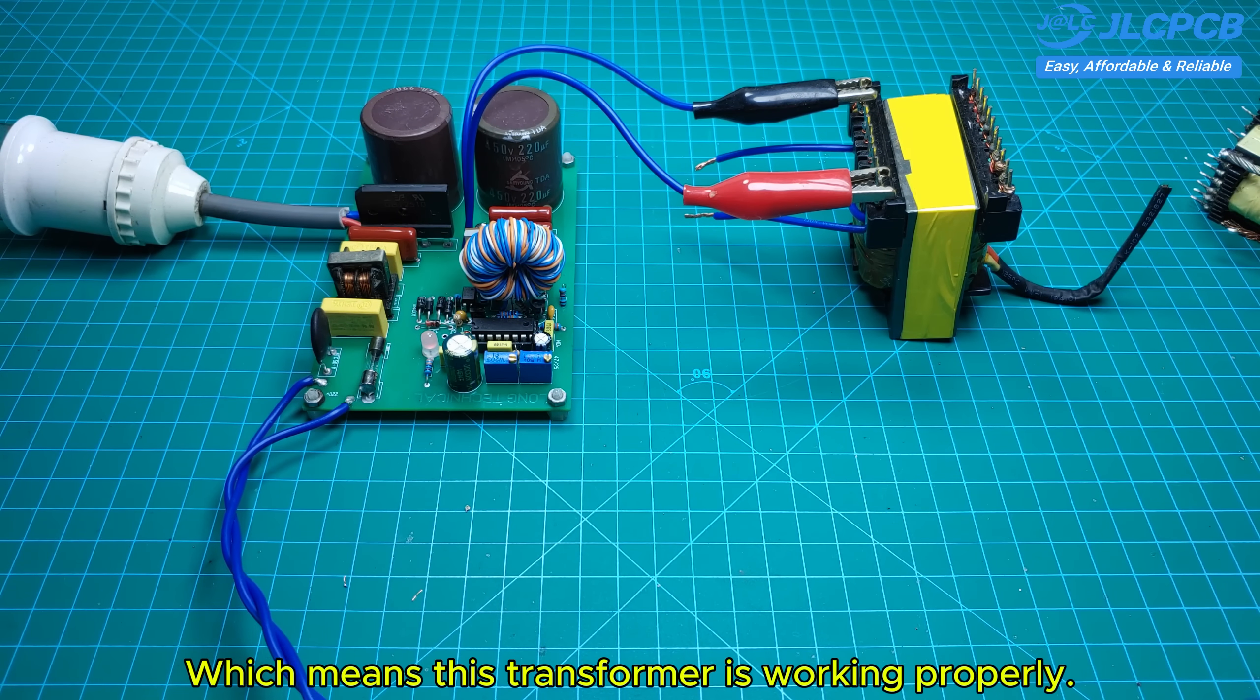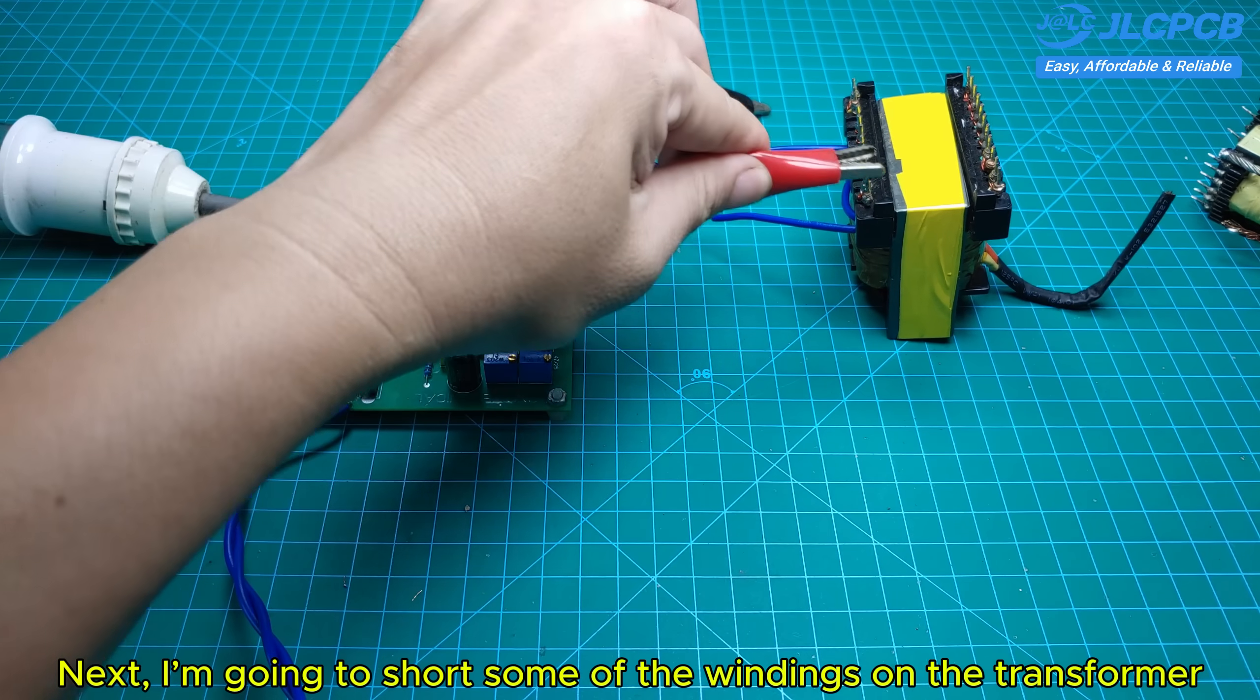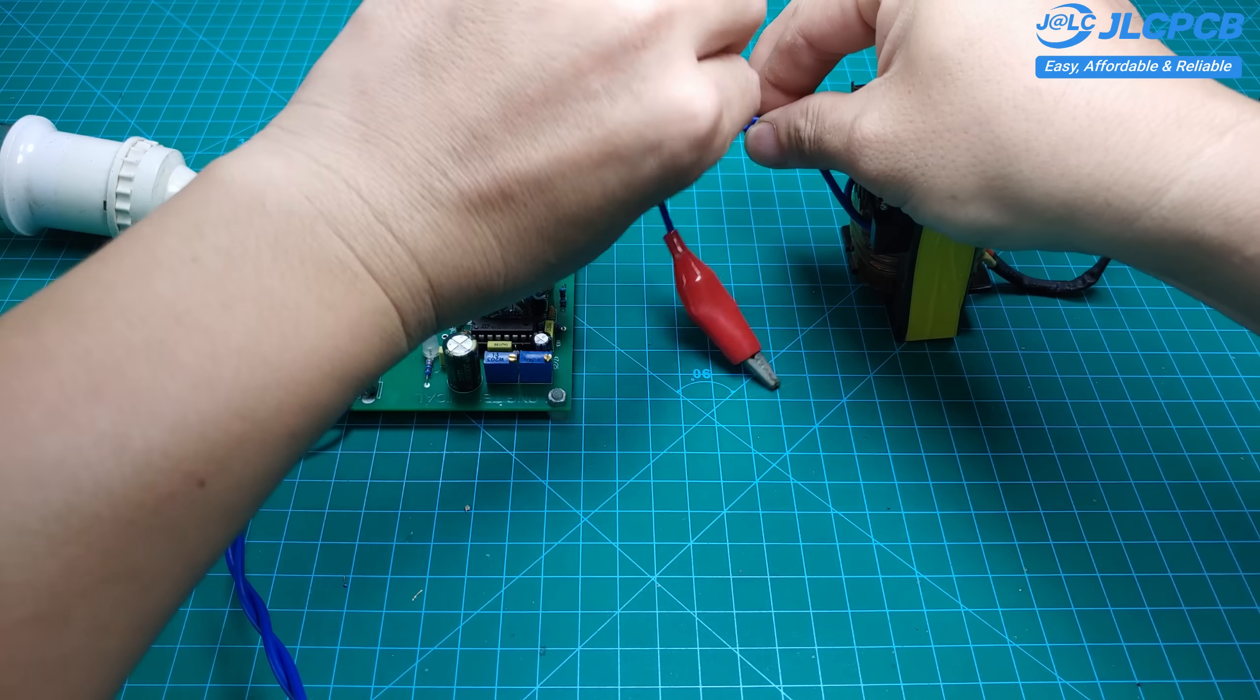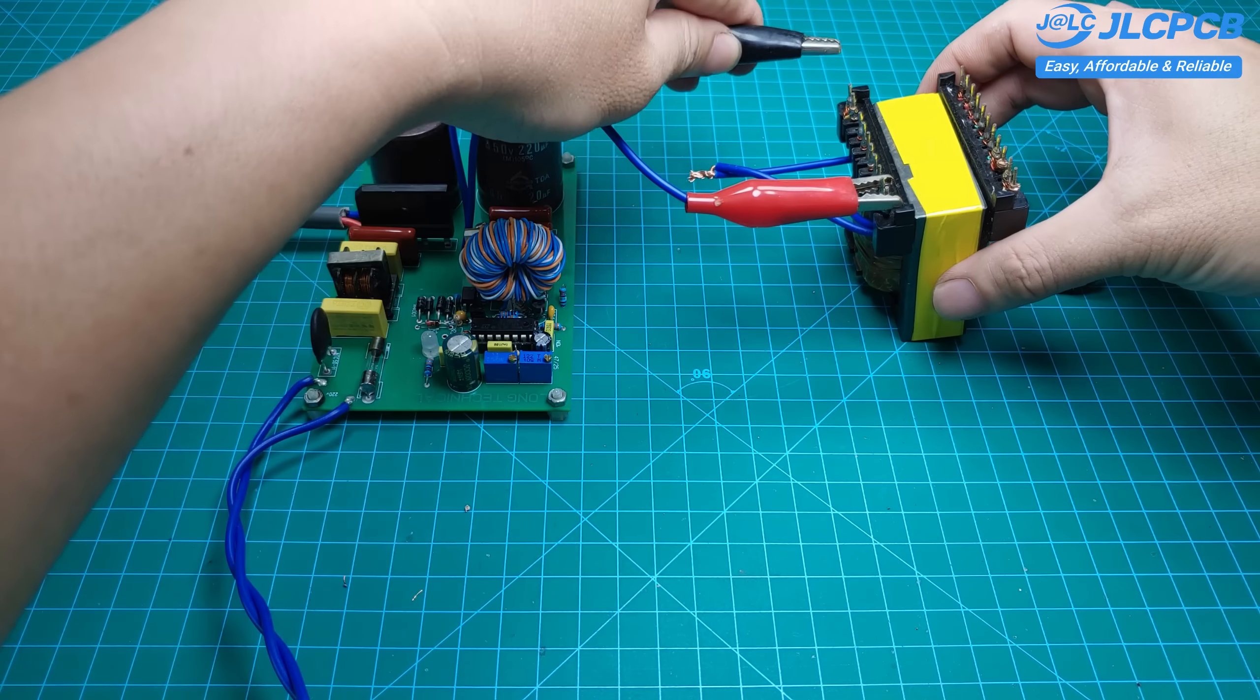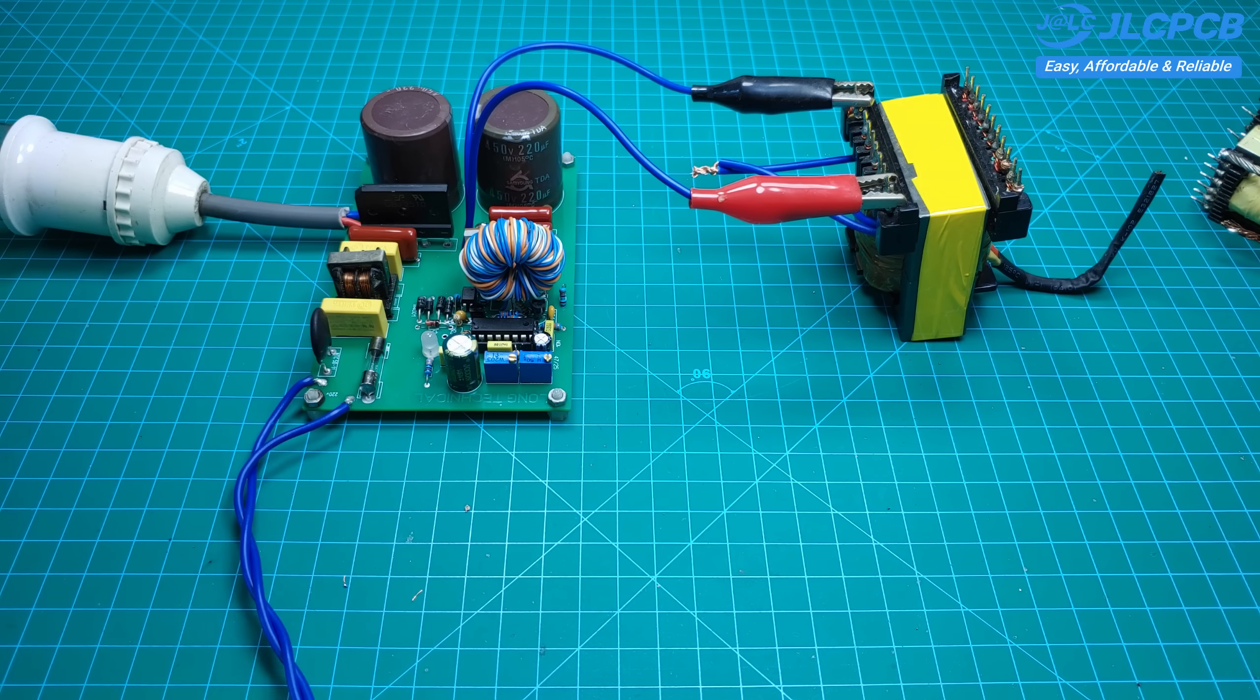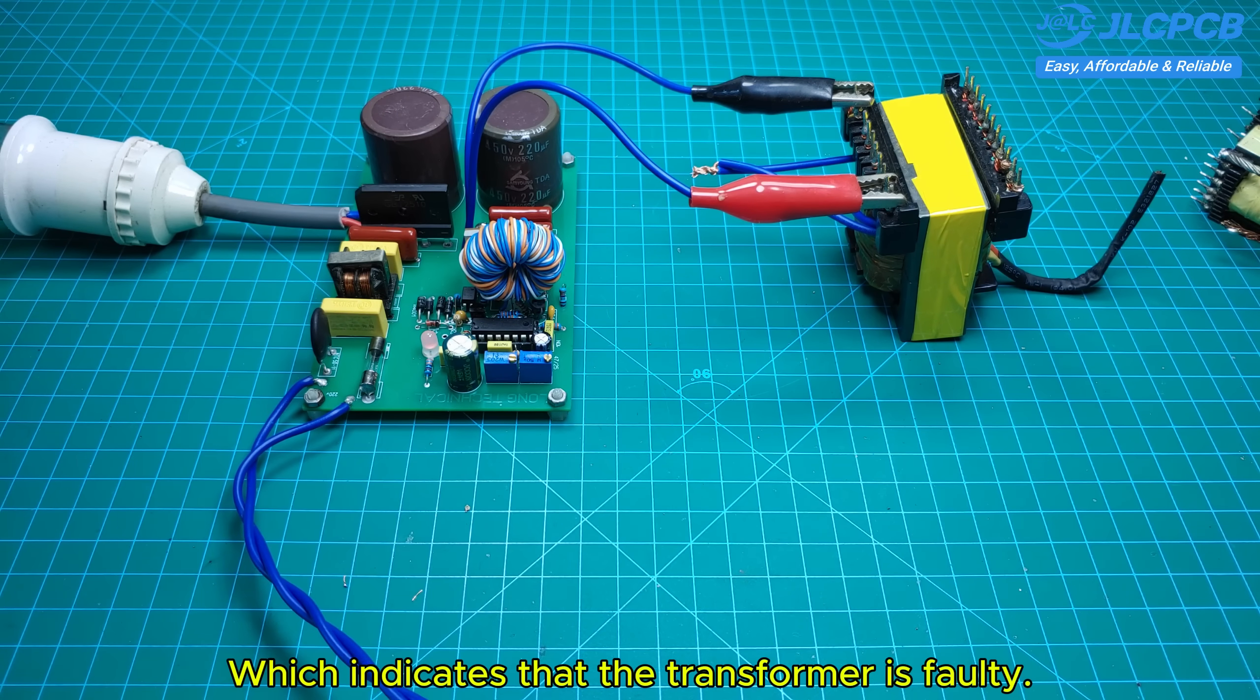which means this transformer is working properly. Next, I'm going to short some of the windings on the transformer to simulate an internal short circuit. Let's see what happens. As we can see, the LED is blinking, which indicates that the transformer is faulty.